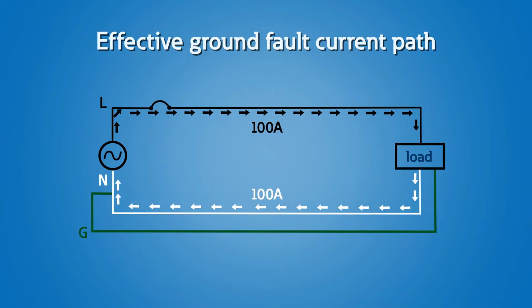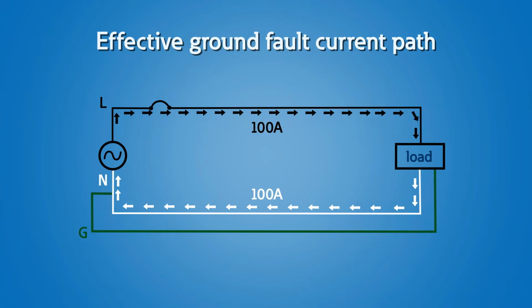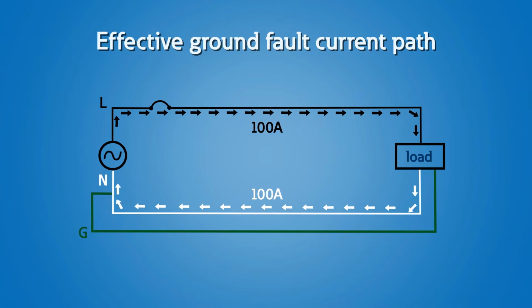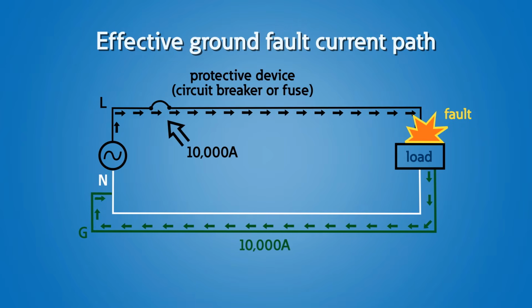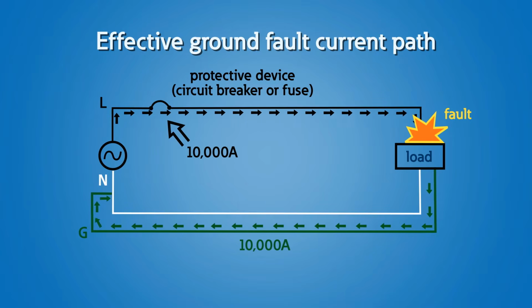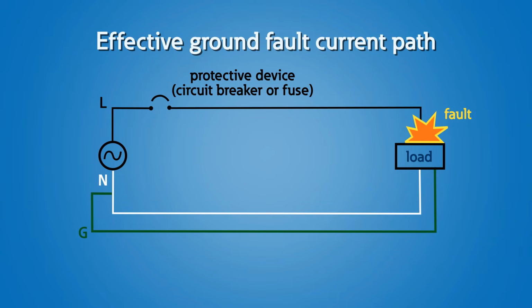Why are we talking about this? Why do we worry about grounding and bonding? We want to establish an effective ground fault path, and we also want to think about touch potentials or step potentials, for two different reasons. First, the effective ground fault current path: we're intentionally constructing a low impedance conductive path that's designed to carry the fault current from the point where the ground fault occurs in the system back to the source. And the reason we do that is we want to make sure that we open the overcurrent protective devices, which could be equipped with ground fault protection of equipment or GFCI protection. We want to make sure that we open those and give enough current for those to detect that fault.